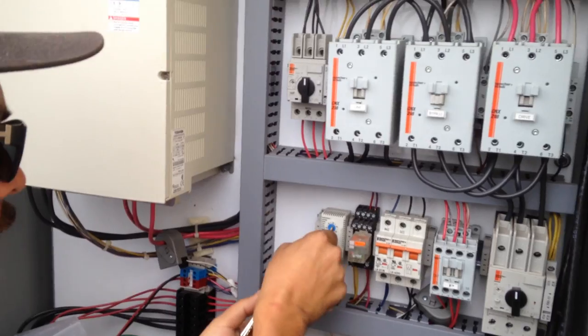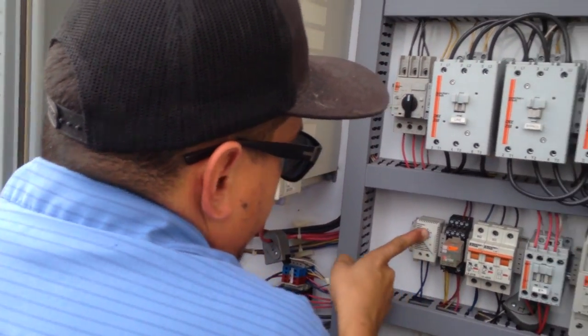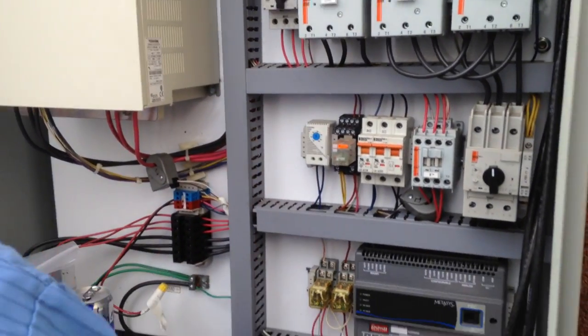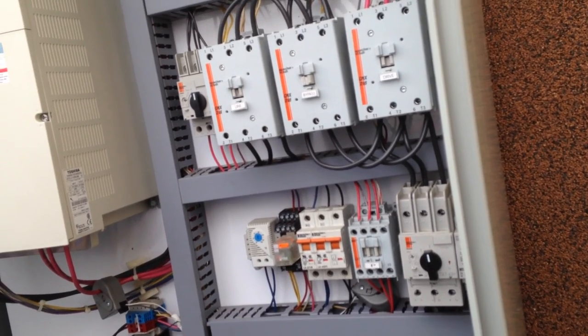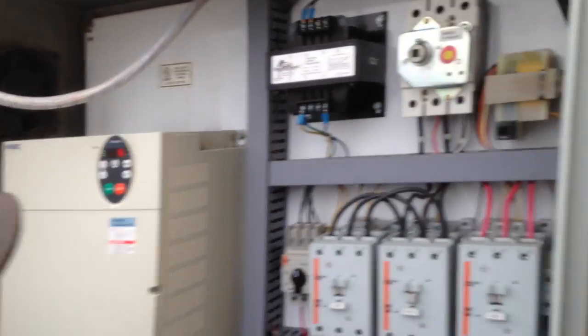Give me a second, because I'm already finding an issue with this. We do have an issue at this time. Do you have a little tweaker? I have it in my van, I don't have one on me unfortunately. We have an issue because this fan's not spinning, and that usually keeps the controls cool — keeps the air flowing.